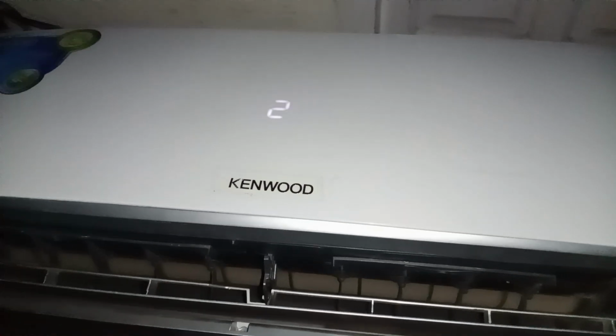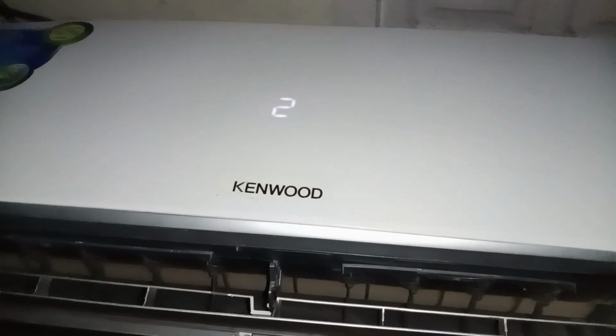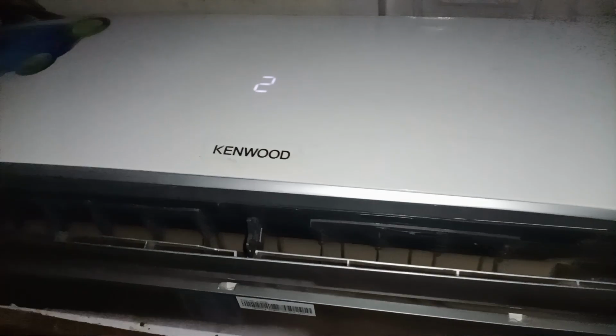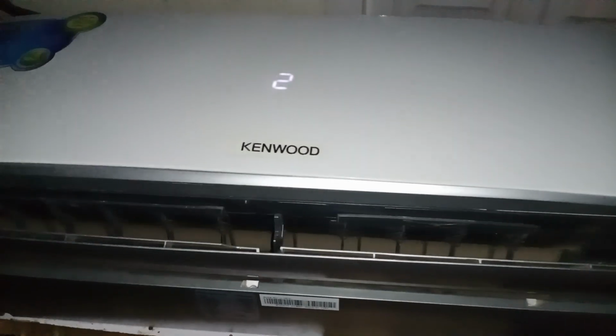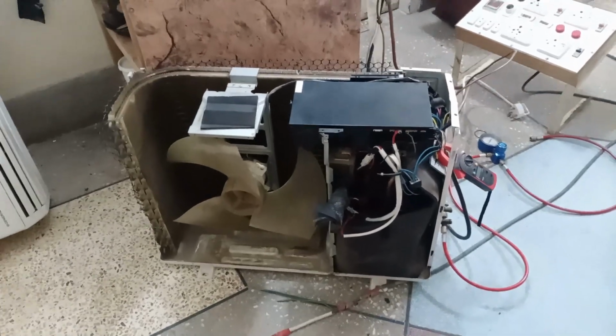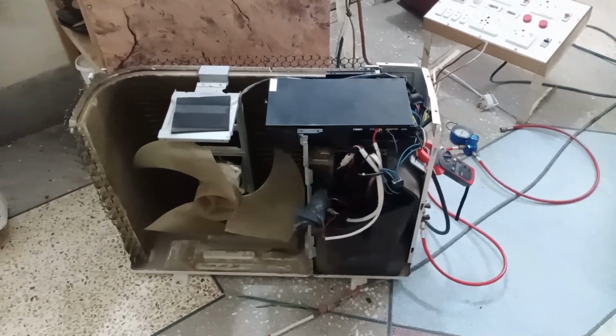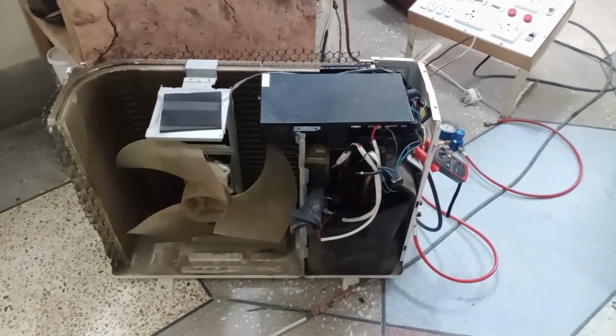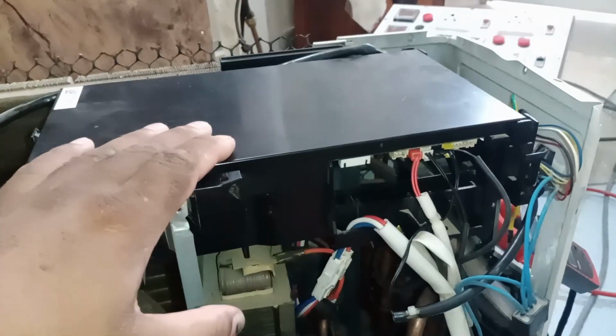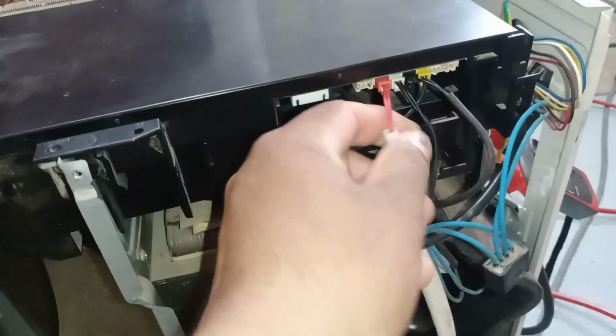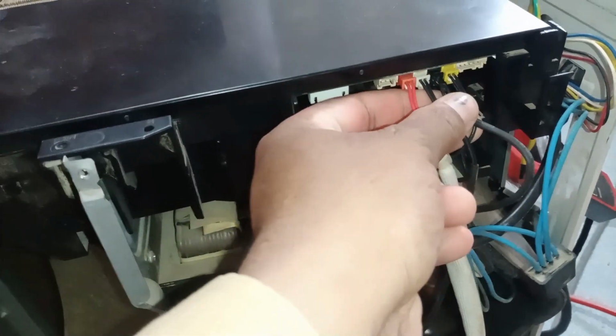This mini-split air conditioner is blinking error code 2. I will guide you on what this error means, its possible causes, and how to fix it. Now we have moved to the outdoor unit, and whenever error code 2 appears on the display, it indicates a fault in the outdoor unit. You can see this PCB and the sensors connected to it. Now I will tell you which sensor is faulty.